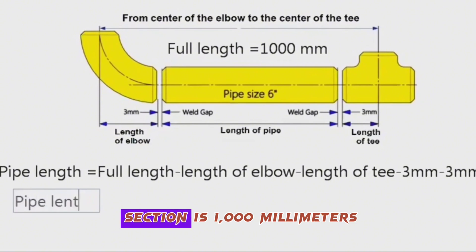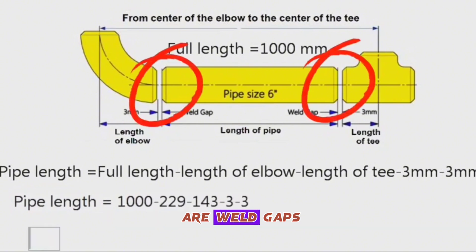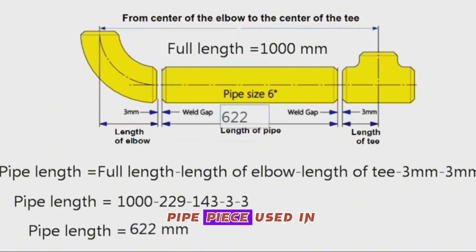If the full pipe section is 1000 millimeters, then the pipe length is equal: 1000 minus 229, minus 143, minus 3, minus 3. In here 3 millimeters are weld gaps which are used in the fit-up stages. Here we calculate and find that the length of the piece of pipe is 622 millimeters. In other words, the length of the pipe piece used in this pipeline is 622 millimeters.